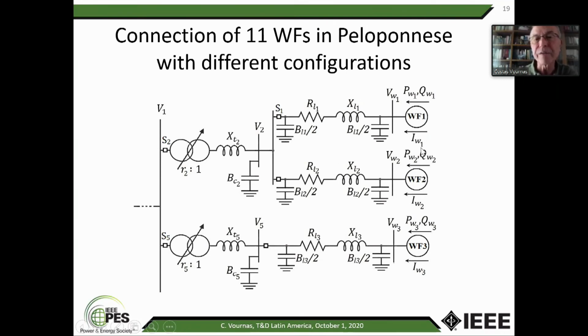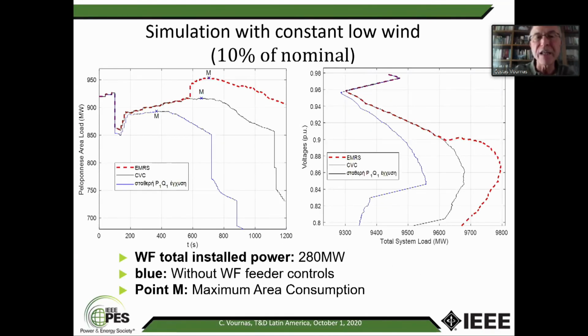because the way they can offer reactive support depends on their voltage and also on their maximum current. You also see the tap changers here and the capacitor banks that are coupled with each transformer. Again, we assume the same type of control, so the capacitors are switched in based on V1. The tap changers are controlling V2 or V5, and the wind farm converters can have any of the controls that I showed before. So if we take a case with constant low wind, which is roughly 10% of nominal.